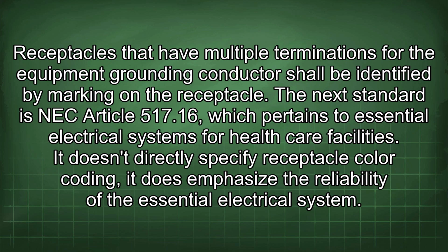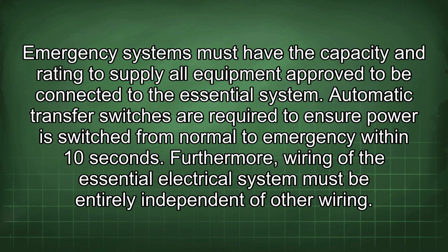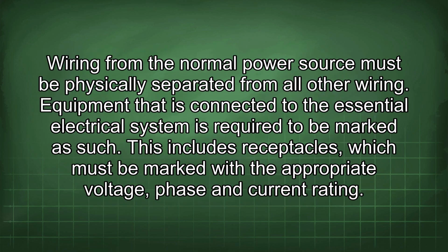It doesn't directly specify receptacle color coding, but it does emphasize the reliability of the essential electrical system. Emergency systems must have the capacity and rating to supply all equipment approved to be connected to the essential system. Automatic transfer switches are required to ensure power is switched from normal to emergency within 10 seconds. Furthermore, wiring of the essential electrical system must be entirely independent of other wiring. Wiring from the normal power source must be physically separated from all other wiring.